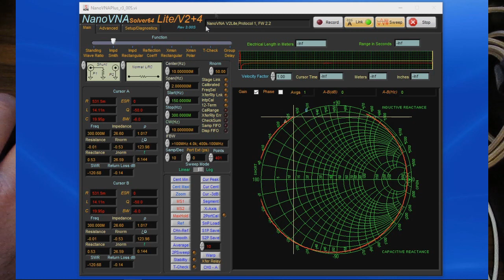We can just enable that, and you can see in the top of the screen, it shows the current number of averages. This is a round robin type average. So for an average of 10, for example, that means the software will store 10 individual sweeps. So as it's collecting a new one, it's throwing off the oldest and averaging the most recent. Of course, it also has this smooth feature, and it also has this max hold. And you can see again, if we turn off the averages, you can see now how our noise level is increasing. The software also supports the firmware averaging, and that's done with this button here.